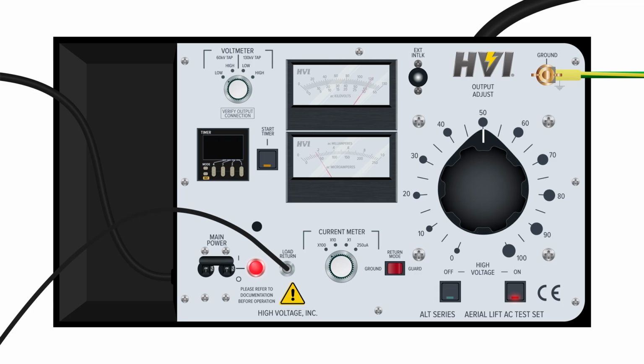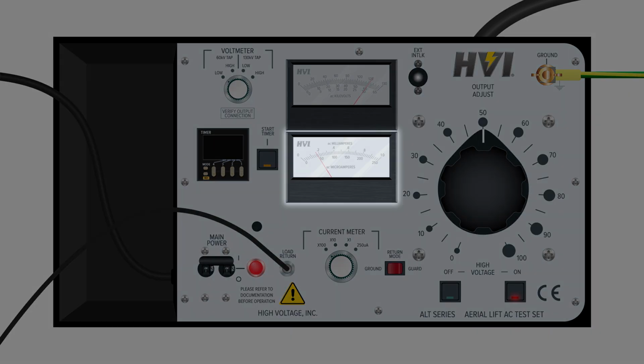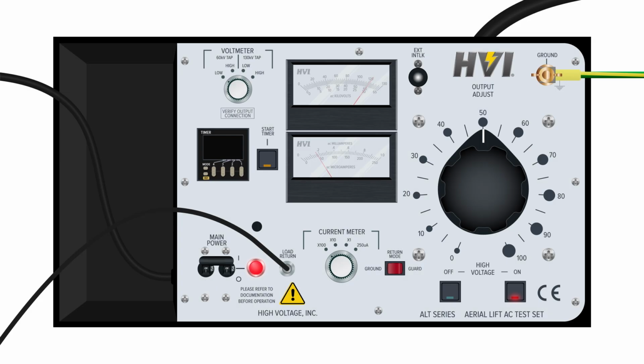Once the high voltage circuit has energized, slowly turn the voltage output clockwise to increase the supplied voltage. The voltmeter will now display the voltage. Raise the voltage to the intended amount for the DUT. Now note the amount of current that's displayed in the current meter. If the current meter display doesn't move much, switch to a lower range for optimal readability, to ×10 or ×1. When the meter display settles between 0 and 1, measure the amount of current as indicated by the meter.